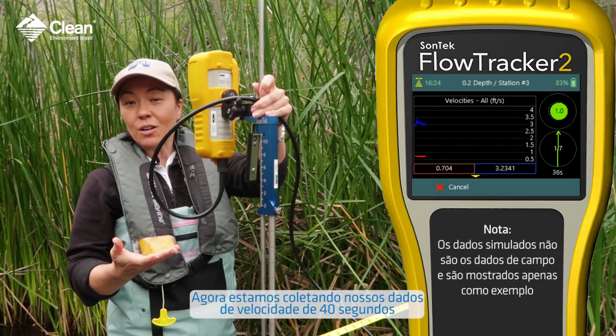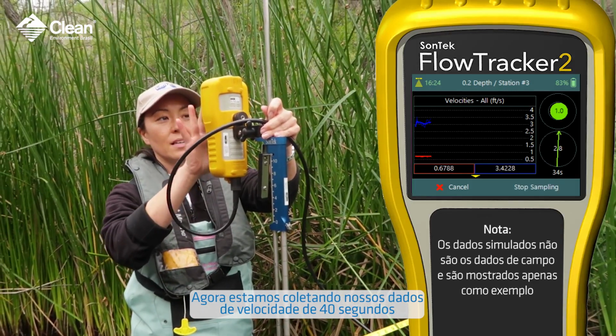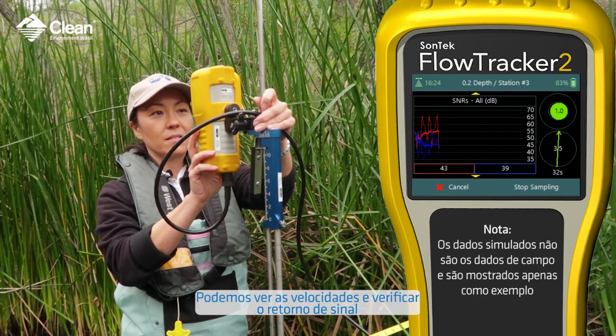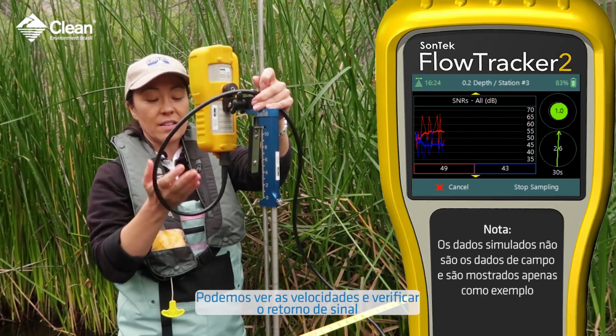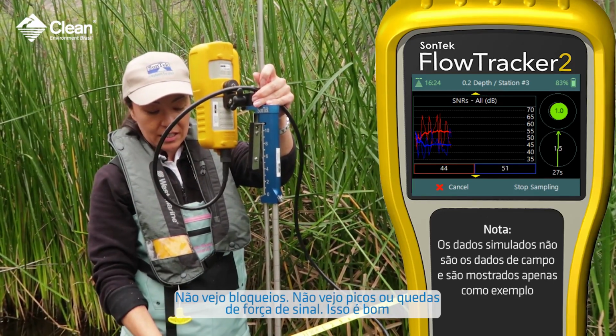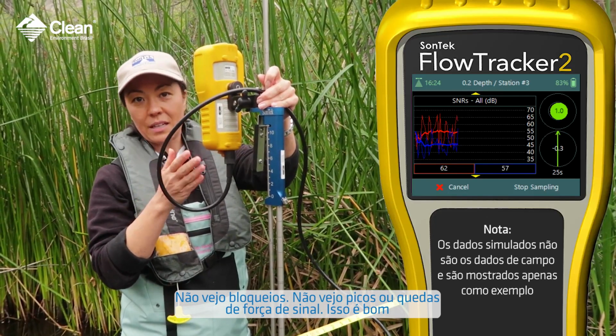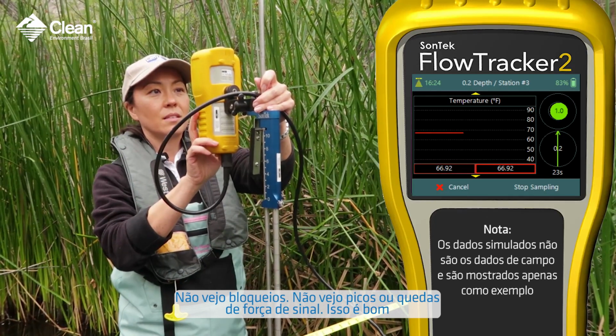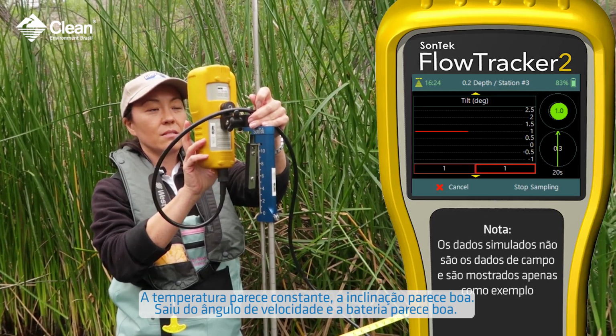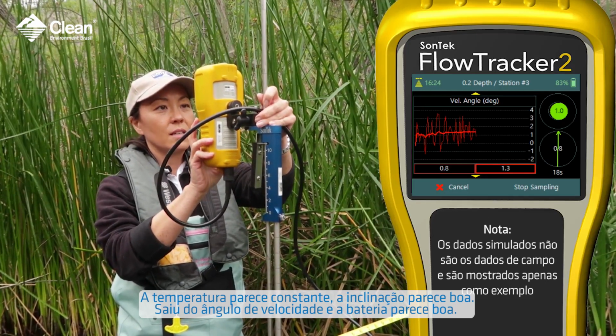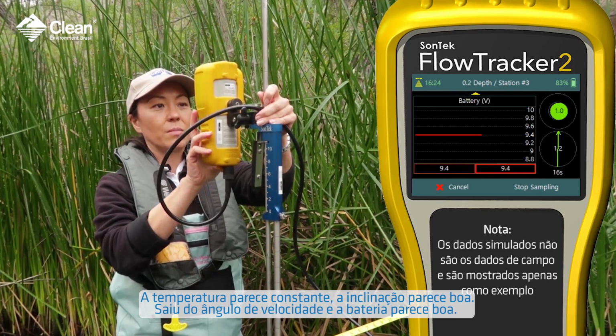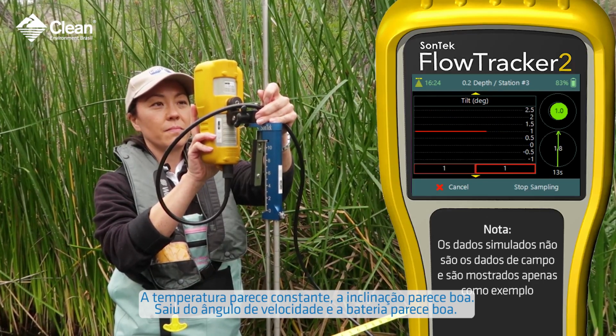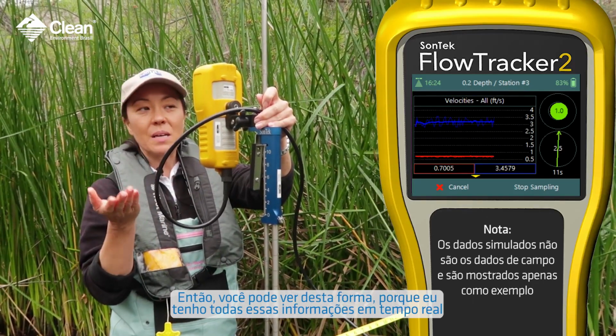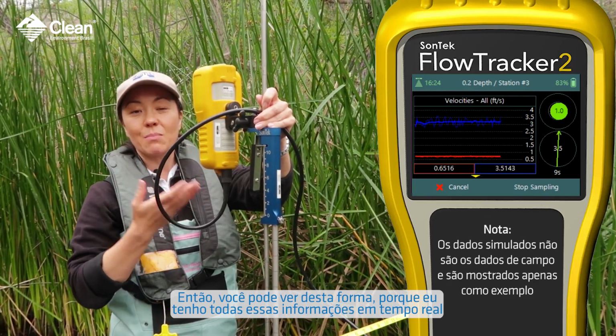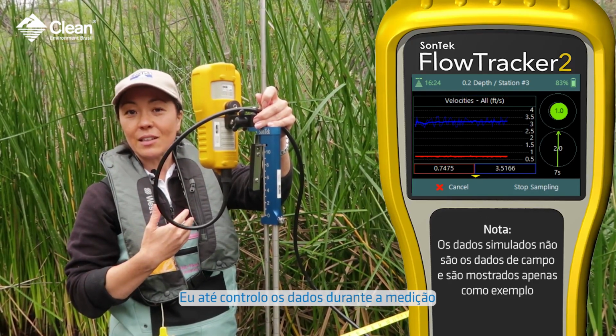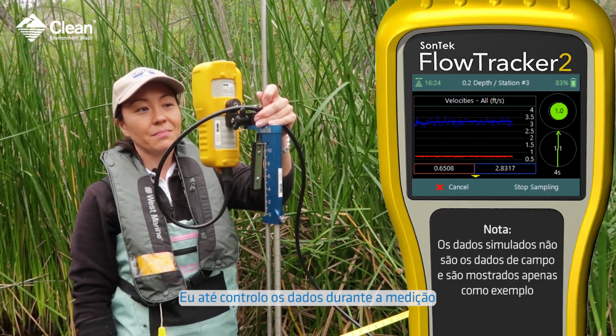Now we're collecting our 40-second velocity data. We can see the velocities. We can verify the SNRs. I don't see any blockages. I don't see any signal strength spikes or drops. That's good. Temperature looks constant. Tilt looks good. Got our velocity angle and battery. Looks good. So you can see in this way, because I have all of this information in real time, I'm even QCing the data during the measurement.